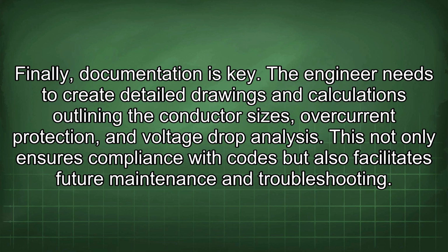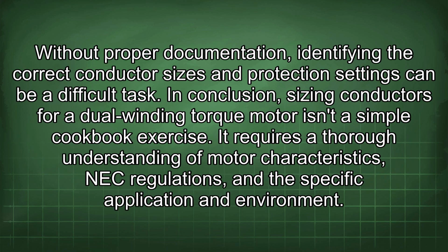Finally, documentation is key. The engineer needs to create detailed drawings and calculations outlining the conductor sizes, overcurrent protection, and voltage drop analysis. This not only ensures compliance with codes but also facilitates future maintenance and troubleshooting. Without proper documentation, identifying the correct conductor sizes and protection settings can be a difficult task.